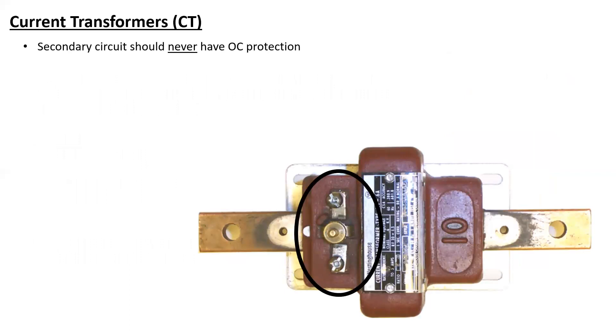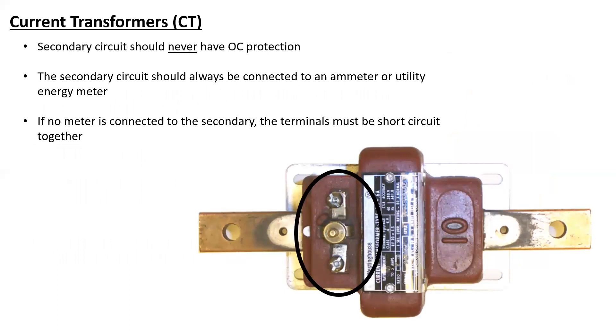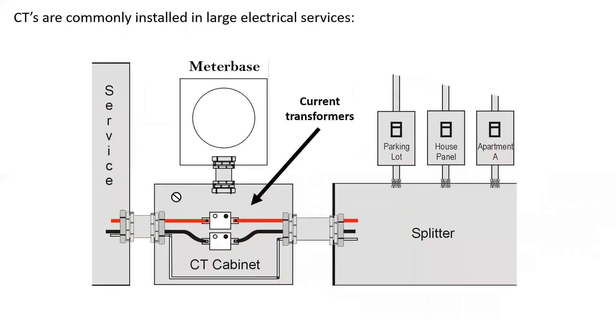Again, the secondary circuit of a CT is never to have an overcurrent on it, and it should always be connected to an ammeter or utility energy meter. And again, if no meter is connected to the secondary, the terminals must be short-circuited together. And usually, there is a bar provided by the manufacturer that is mounted to the equipment that allows us to do this quite easily.